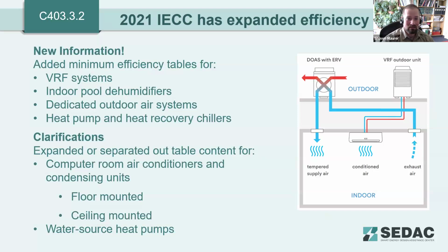The 2021 has expanded the equipment efficiency table significantly. It's added in specific efficiency tables for VRF systems, indoor pool dehumidifiers, dedicated outside air systems, and heat pump and heat recovery chillers. And then it's added some clarification on some other tables by expanding or separating out content that was previously contained in the 2018. So computer room air conditioners and condensing units have been separated out into their own table and have different requirements for floor mounted versus ceiling mounted systems. And water source heat pumps have been broken out separately from other heat pump type systems into their own table as well. So that's expanded the number of tables. In the 2018, it was 10 tables. There are now 16 different reference tables for unit efficiencies.